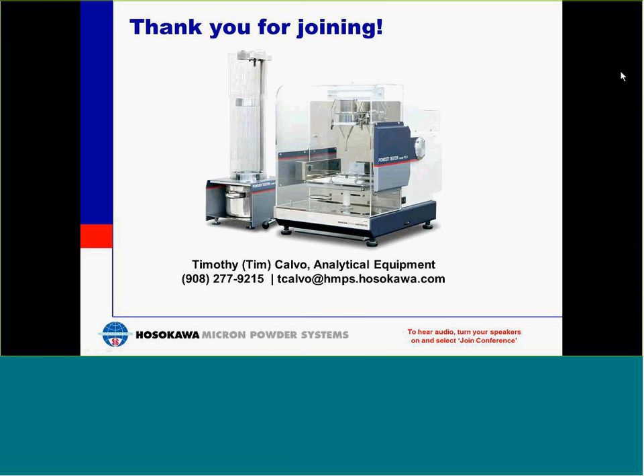So the question is, what's the proper technique for cleaning this instrument? Well, quite frankly, what we do here at Hosokawa Micron Powder Systems is any dry powder, we'll utilize a vacuum to clear any of the loose powder, but the rest of the equipment can be washed in a wash basin. They have stainless steel, and it's quite easy. There's nothing to prevent you from washing, letting it air dry, or even drying it manually by hand. There's no major issue there.